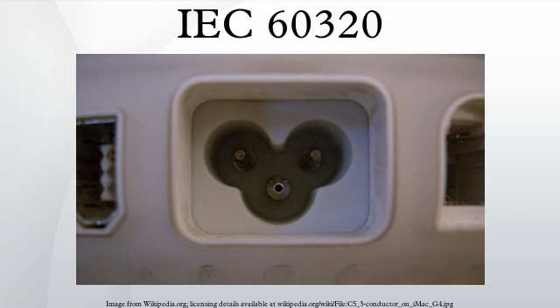Withdrawn and other standard sheets, some connector types are no longer in the current standard. The C3 and C4 standard sheets, and the C11 and C12 standard sheets, are no longer listed. Standard sheet C25 shows retaining device dimensions. Sheet C26 shows detailed dimensions for pillar-type terminals, where the end of the screw bears on a wire directly or through a pressure plate. Sheet C27 shows details for screw terminals, where the wire is held by wrapping it around the head of a screw.